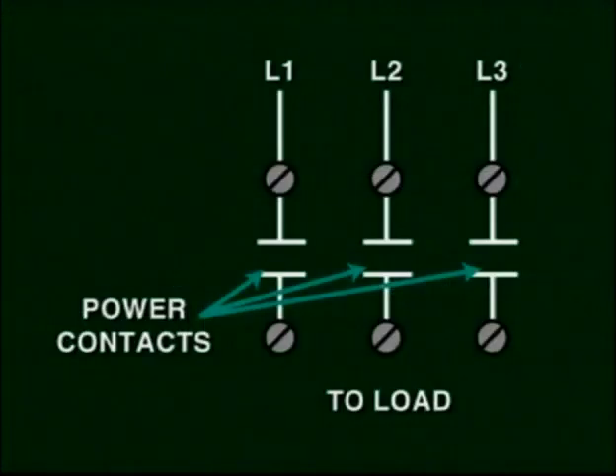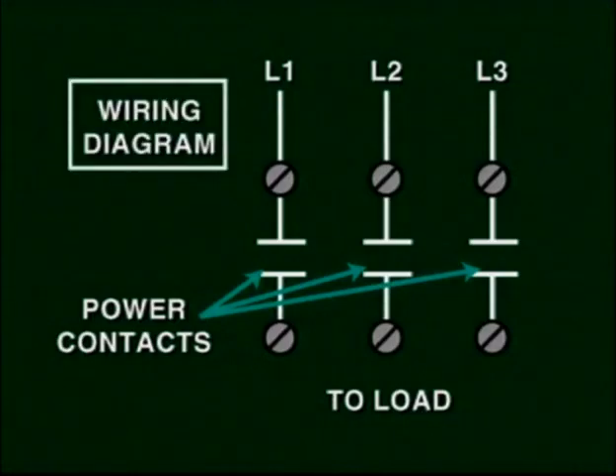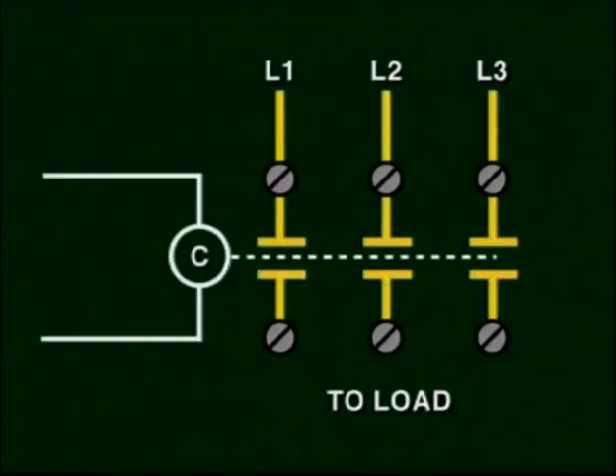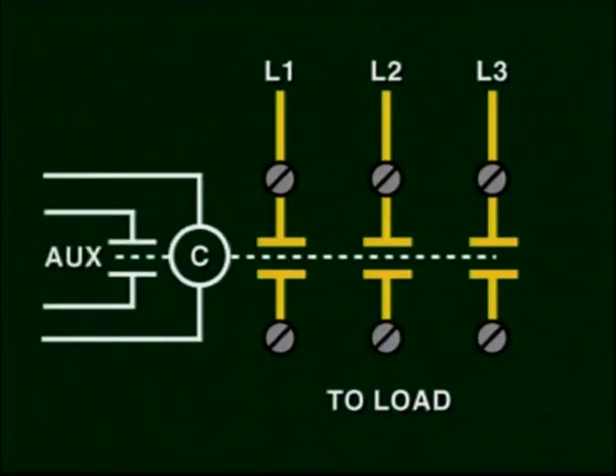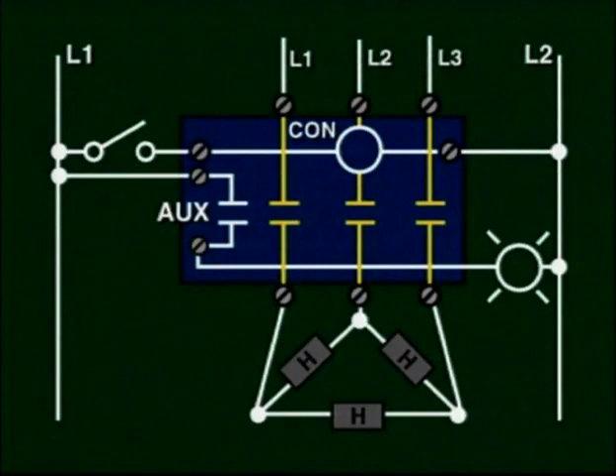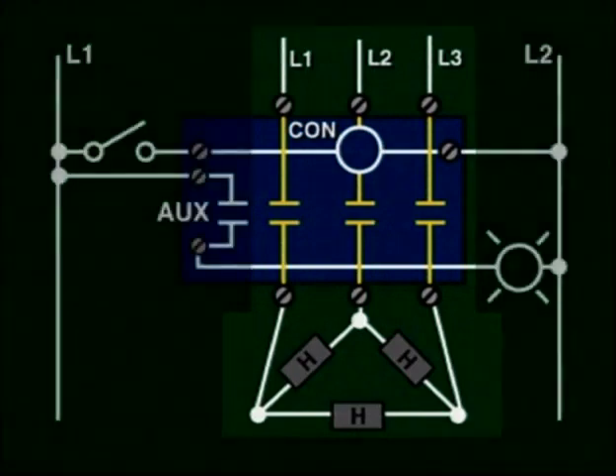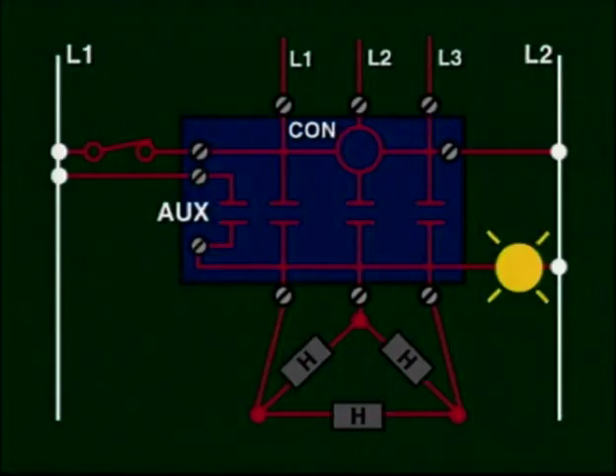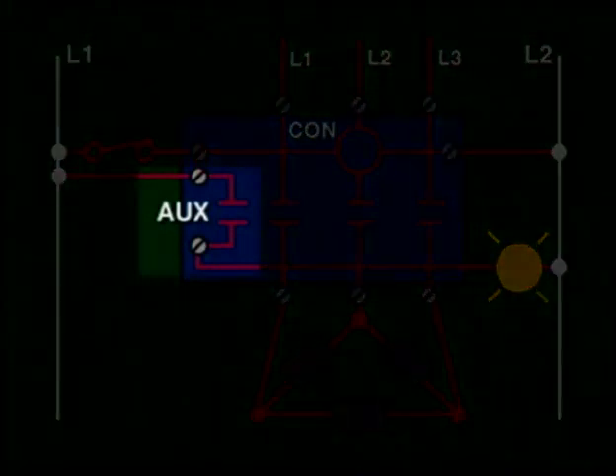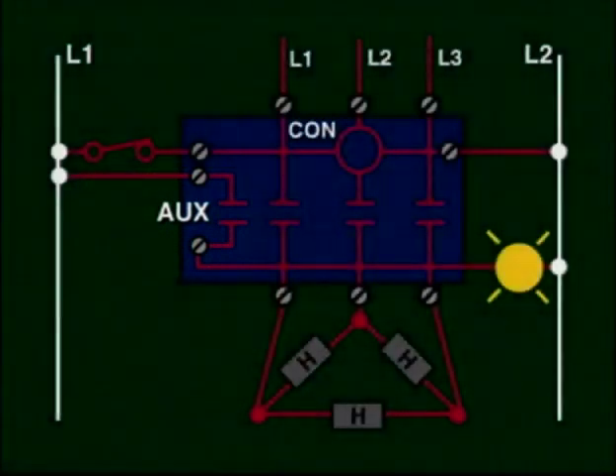Its power contacts, however, are not represented in the ladder diagram, but in another electrical diagram called the wiring diagram. These contactors also have what's known as auxiliary contacts, which react in the same manner as control relay contacts and are not part of the power contact circuit. We could graphically represent a contactor circuit like this, where the three-phase power lines are being switched to the heater. When the switch closes, the contactor's coil is energized, thus closing its power contacts and turning on the heater. The auxiliary contacts of the coil will also close, which, if connected to a light, will make it light up.